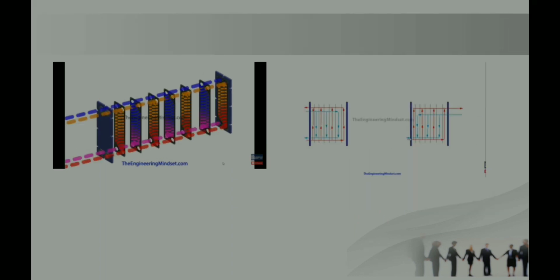In this image, we can clearly see the performance of a plate heat exchanger, with heat absorbed in alternating channels. We enter cold fluid at the top, and heat is transferred from a hot plate and absorbed into the cold plate. This performance happens in alternating fashion and continues continuously, so at the outlet we get a warm fluid where the cold fluid has turned warm. On the other side, we send hot fluid at the bottom; heat is absorbed from the heat plate and transferred to the cold plate, and at the outlet we get a warm fluid at a lower temperature compared to the inlet fluid.